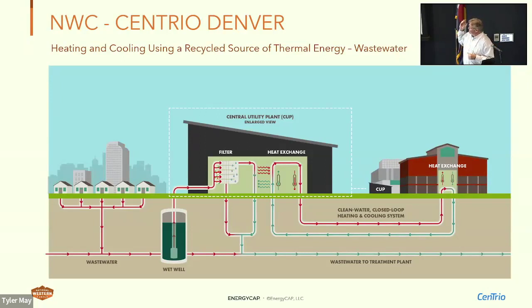Then they bring the water back to us. Now, if we have extreme situations, a really hot spell or a really cold spell, we have boilers for backup, so some package boilers can come on and put additional heat into the loop if needed. We also have cooling towers, so we can put additional heat rejection into the loop if needed. We operate on very close temperature bands. If you were doing centrifugal chillers, you'd be sending out 40-degree water, using a lot of electricity and compression to make that, and cooling towers using a lot of electricity. Same thing with boilers, you'd be consuming a lot of gas.